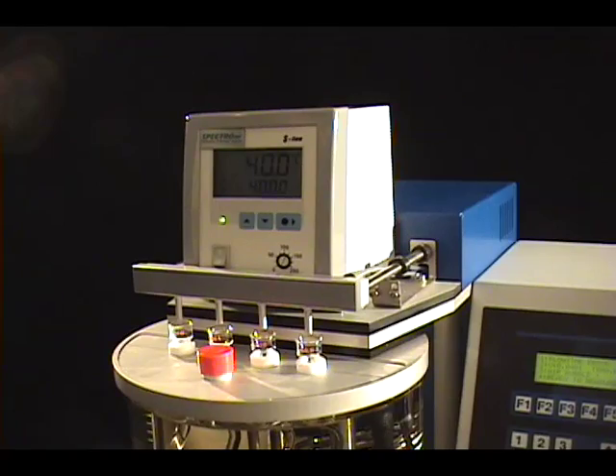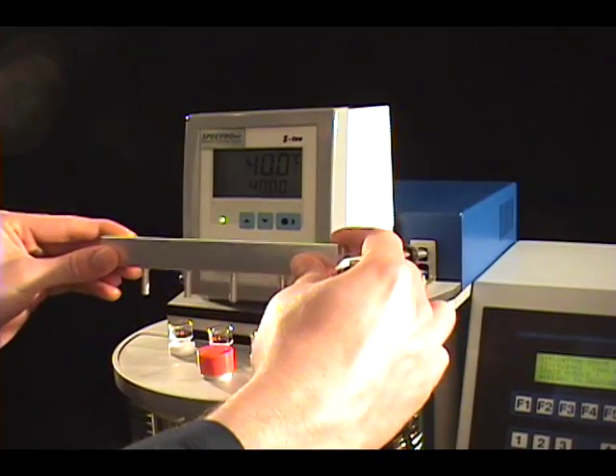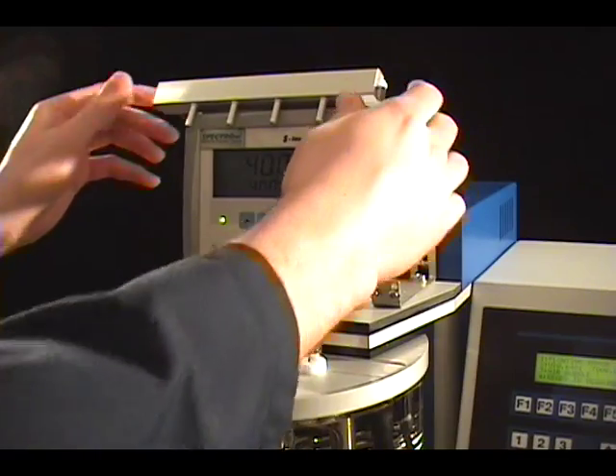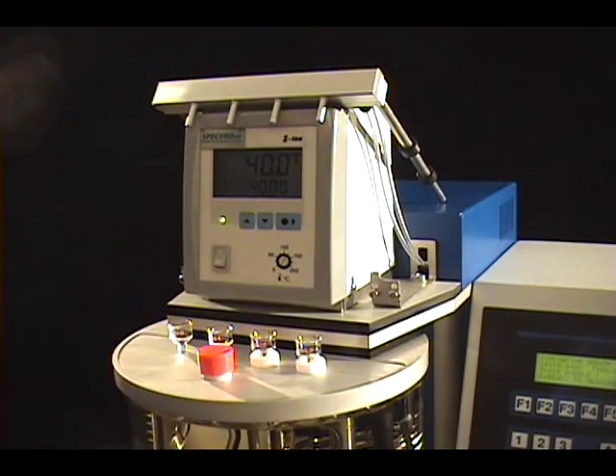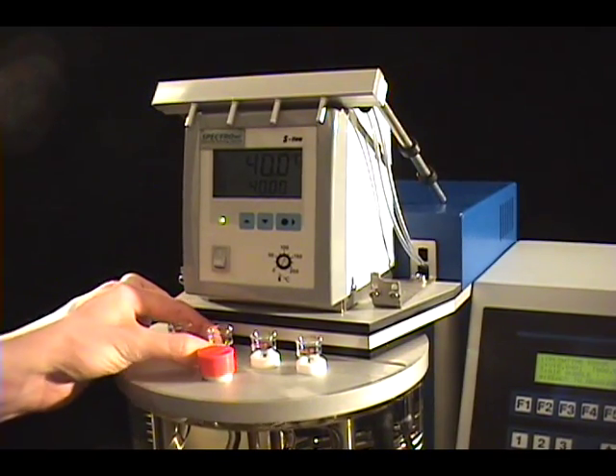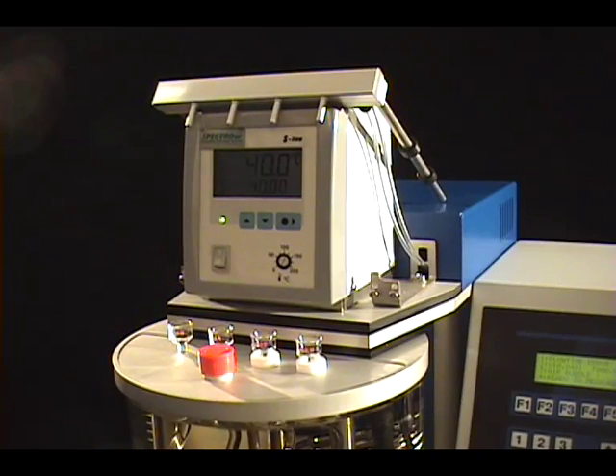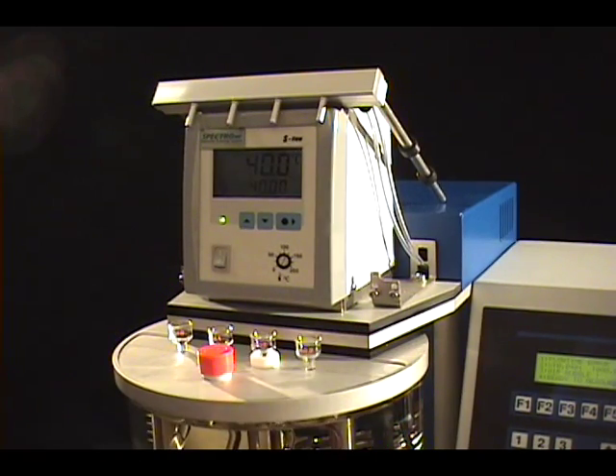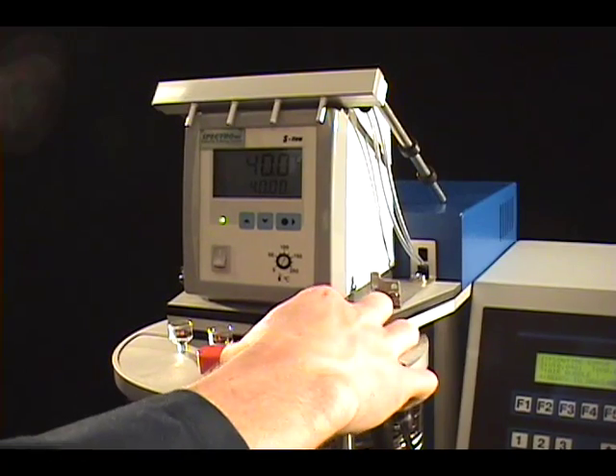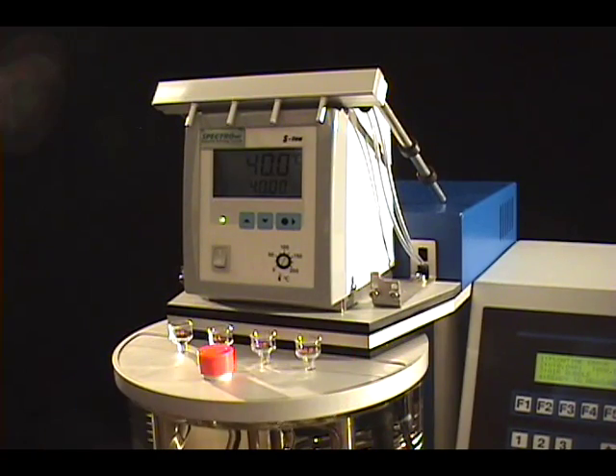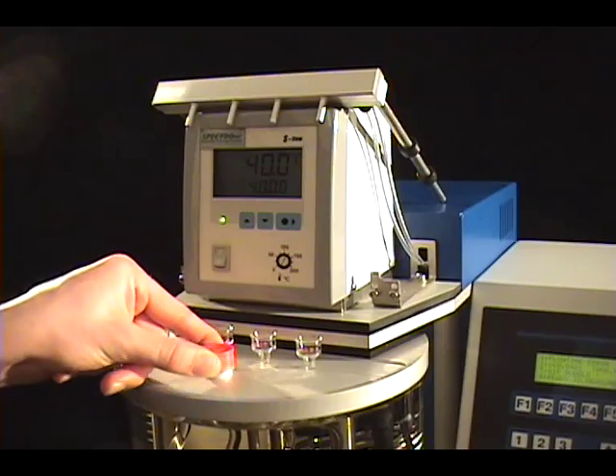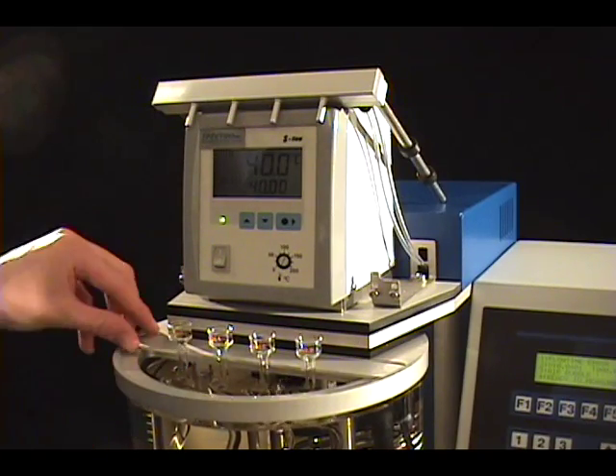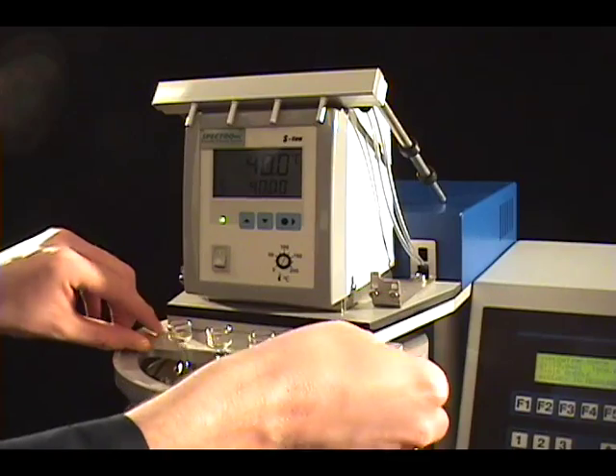To free the top of the glass tube, remove the solvent injector from its holder and place it on top of the thermostat. The white spacers, which ensure constant positioning of the measuring tubes, are removed. By doing this, the thermostatic bath lid becomes accessible. The bath lid, consisting of two parts, is removed.